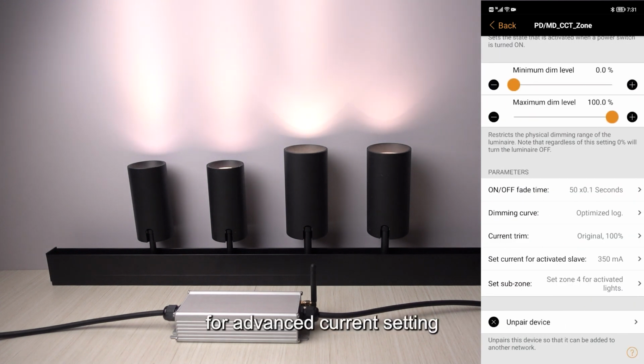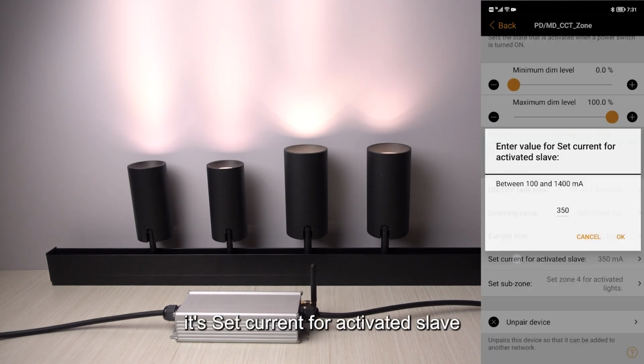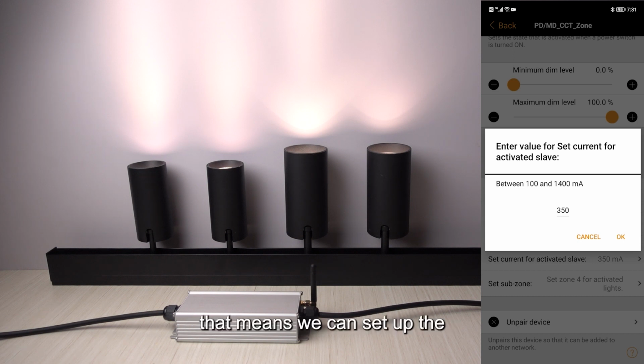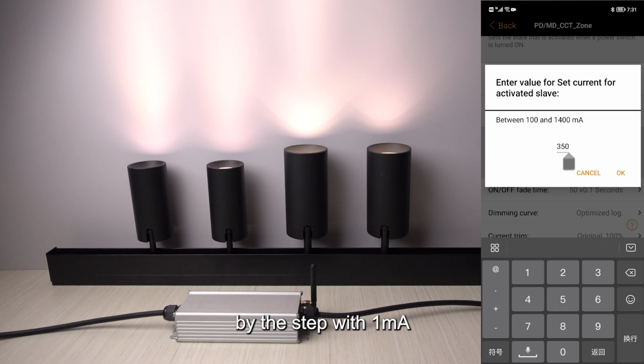And for advanced current setting, we can find the fourth option. It's set current for activated slave. That means we can set up the rated working current of each slave light. We can input the driving current from 100 to 1400 milliamp by the step of 1 milliamp.